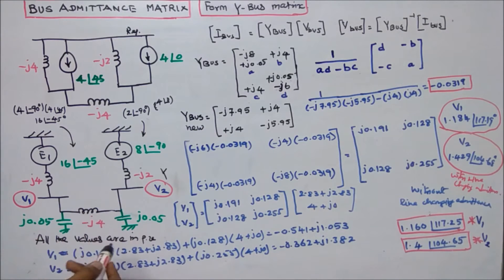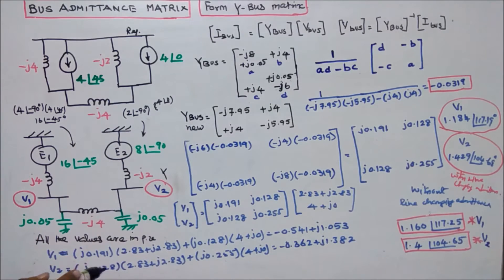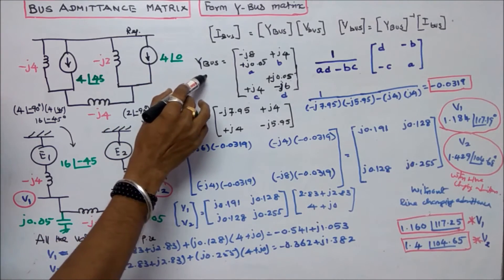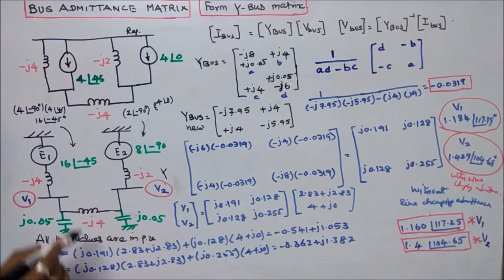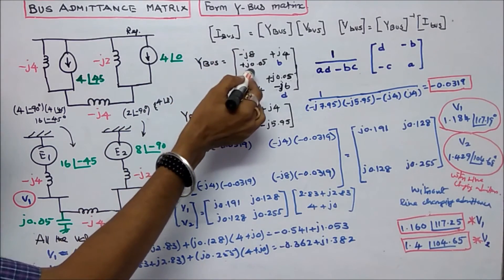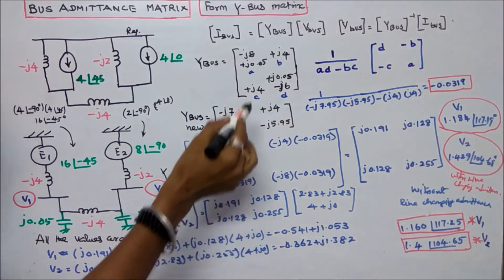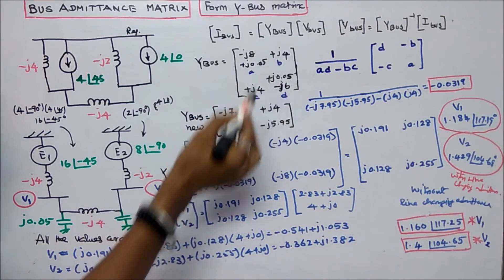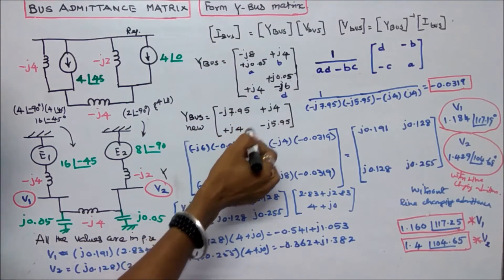In the same problem, we now add line charging admittance of J0.05 and J0.05. The question is to calculate the new Y-bus matrix and also the bus voltages V1 and V2. The old Y-bus matrix was [minus J8, J4; J4, minus J6]. Adding line charging admittance to the diagonal elements: minus J8 plus J0.05 equals minus J7.95, and J0.05 minus J6 equals minus J5.95. The off-diagonal elements remain J4 and J4.